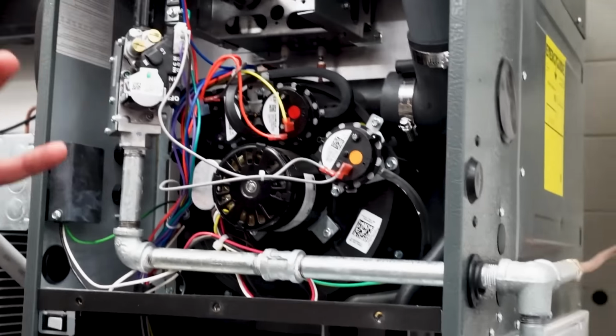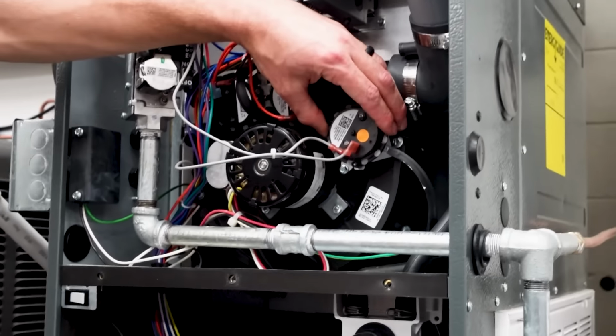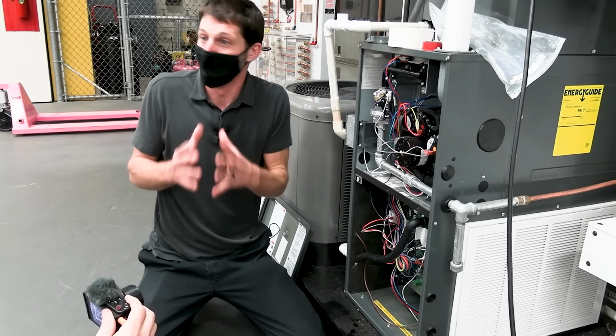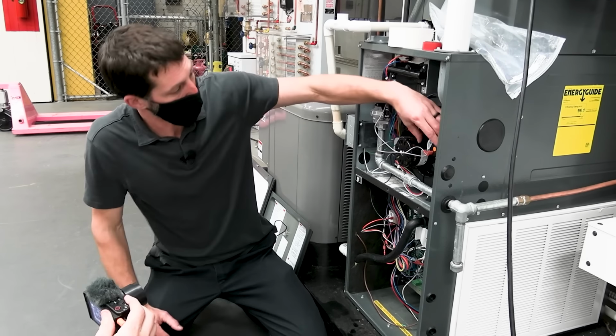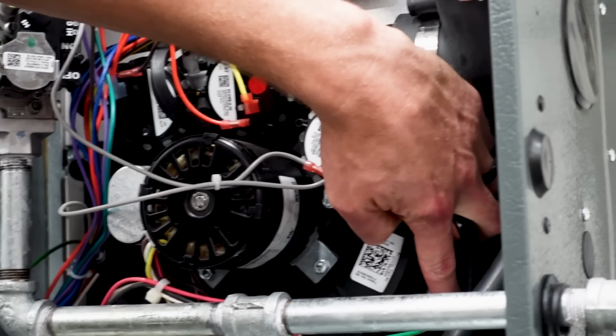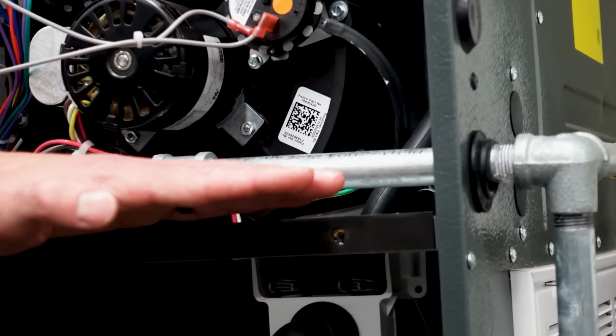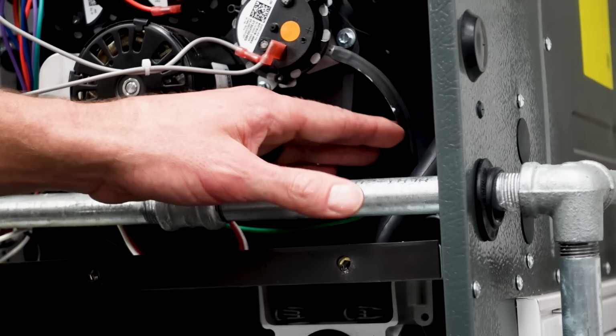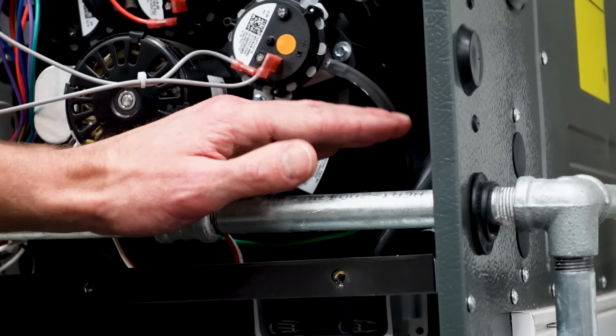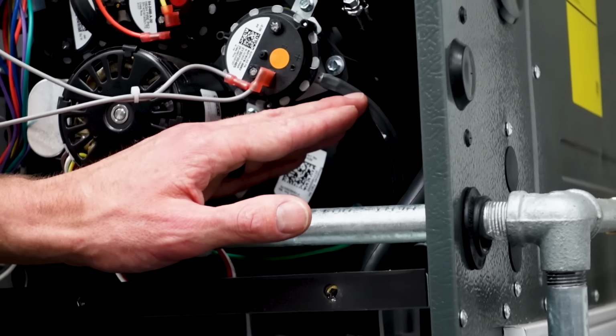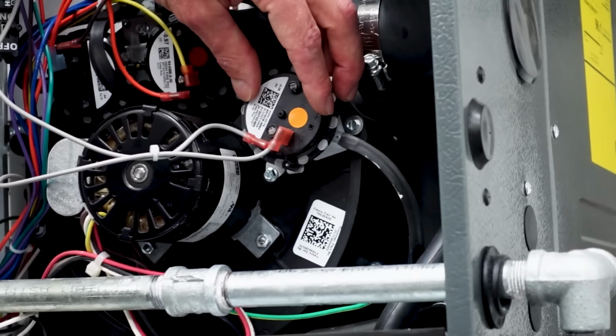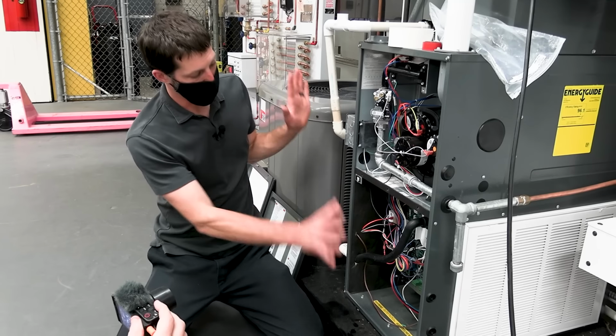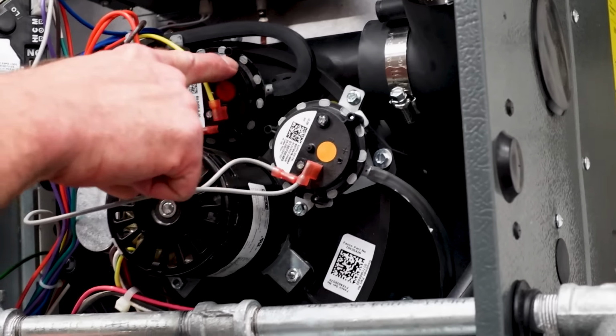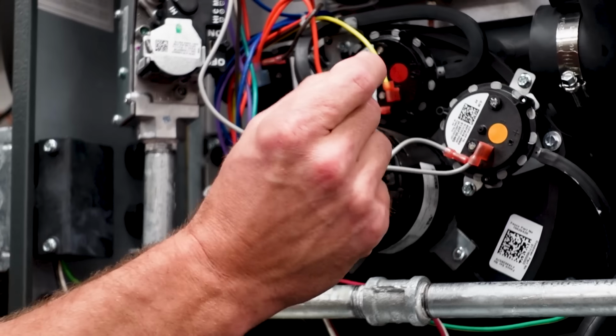But anyway, I'm not trying to pump that tool up or that manufacturer, but the reality is it's a fantastic design. Anyway, this one right here, if this trap clogged and the water level rose above this, then what's going to happen is it's going to shut off the negative pressure on this tube right here, and this pressure switch is going to open up. When this system is off, all of these pressure switches should be in the open position electrically.